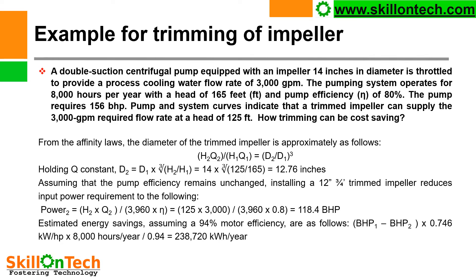From the affinity laws, the diameter of the trimmed impeller is: D2 = D1 × ∛(H2/H1) = 14 × ∛(125/165) = 12.76 inches. Assuming pump efficiency remains unchanged, installing a 12.76-inch trimmed impeller reduces input power to: P2 = (H2 × Q2) / (3960 × efficiency) = (125 × 3000) / (3960 × 0.8) = 118.4 BHP.